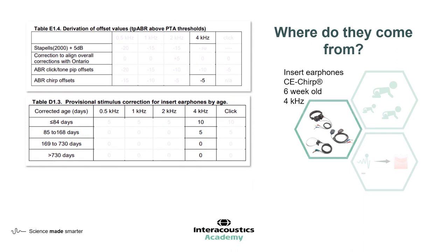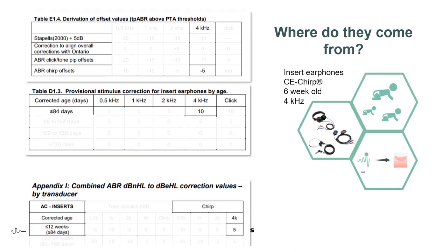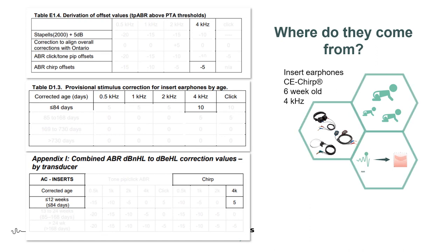Next, we need to consider our transducer correction factors. In this case we used insert earphones at the four kilohertz range. These are divided by age, so we need to make sure we select the correct age band. We are dealing with a six-week-old, so that's the under-84-day category, and that gives us a correction factor of plus 10 for inserts for this age group at four kilohertz. So we have an ABR offset of minus five and an insert age-related correction of plus 10. When we combine those together, minus five plus 10 gives us a correction factor of five — and our combined correction factor document gives us that combined value.